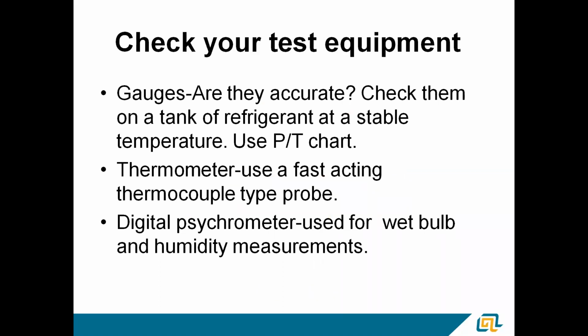So hook your gauges up to a stable tank of refrigerant at a stable temperature. Use the pressure temperature chart to make sure your gauges are accurate. A lot of guys are using the electronic gauges now. Works the same way with those. Should still check them for accuracy, because I do believe they have a tendency to maybe get a little out of calibration. As far as a thermometer for checking TD across a coil or something, I strongly recommend the use of a fast-acting thermocouple type probe.